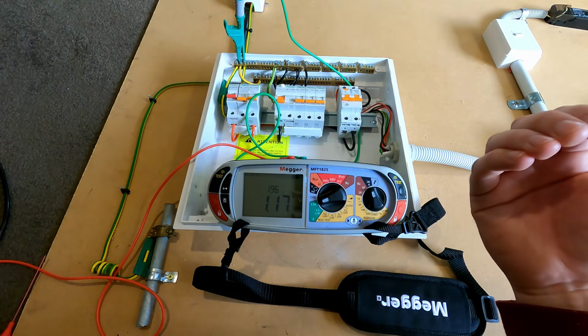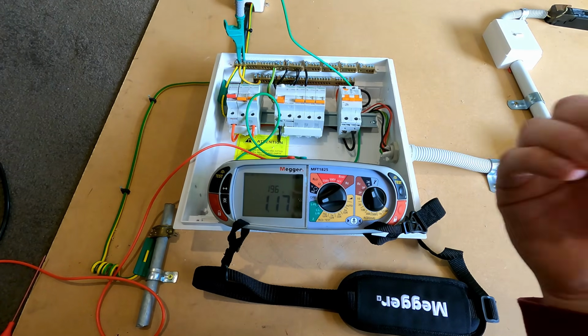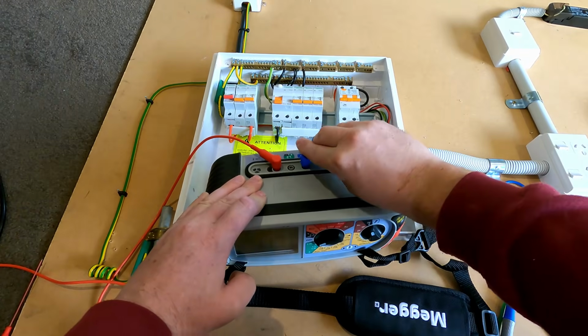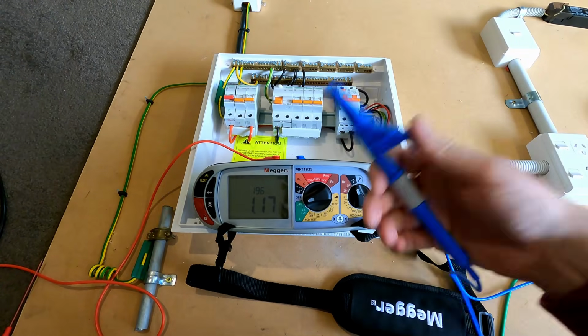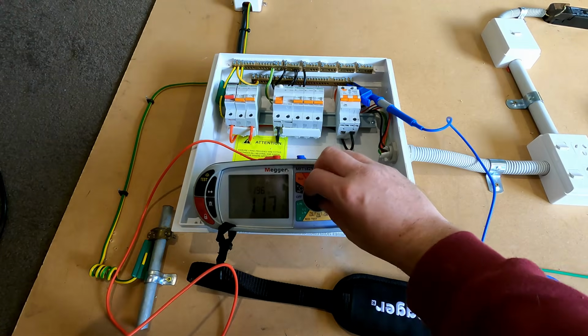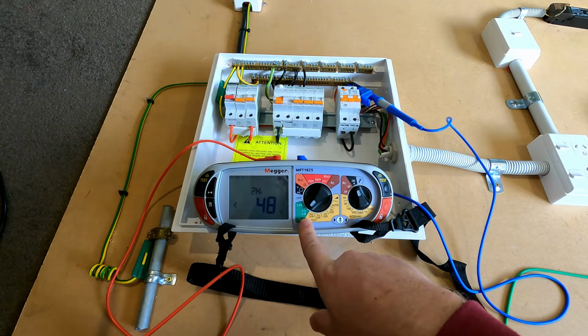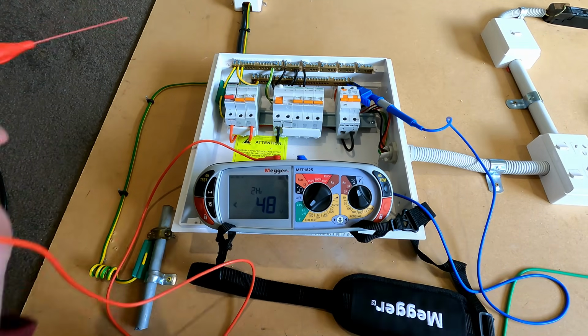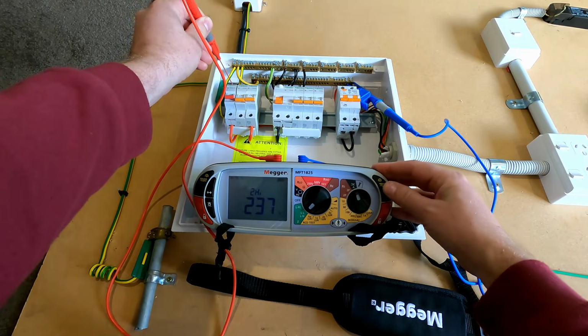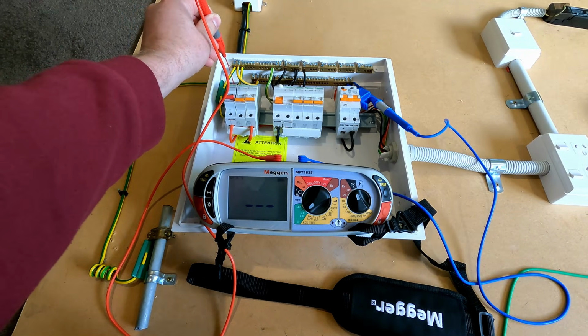So the next test we'll be doing is going to be our neutral. But we'll be doing our 2 lead high on the neutral. So we put this one on the neutral bar, change the setting to line to neutral, and we're ready to test.